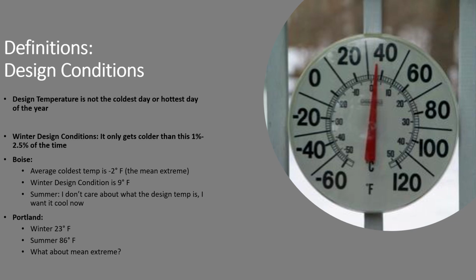Winter design conditions, you can find them for 1% or 2.5%. What that means is it only gets colder than that given temperature, say at 1% of the hours in the wintertime. For Boise, the average coldest temperature is -2. That's referred to as the mean extreme. Winter design is 9 degrees. That gives you quite a bit of leeway. Summer, let's face it, I don't care what the design temp is, I want it cool now.